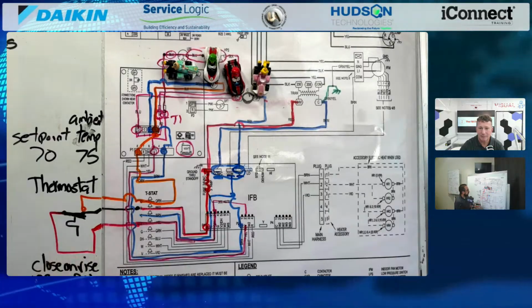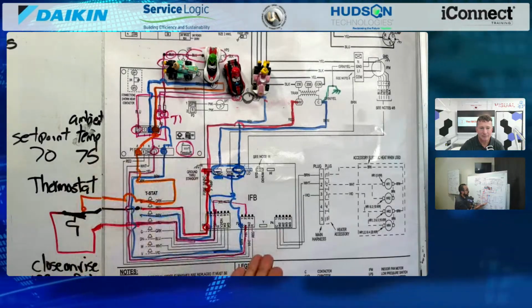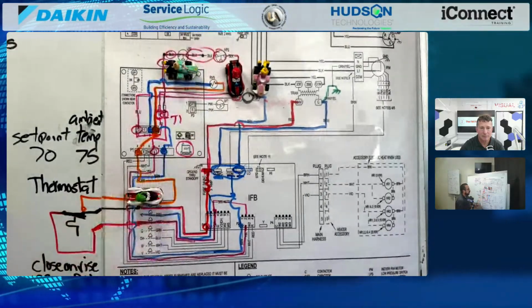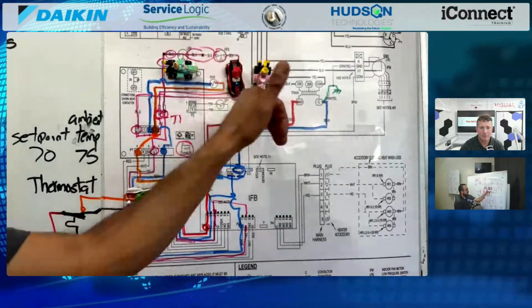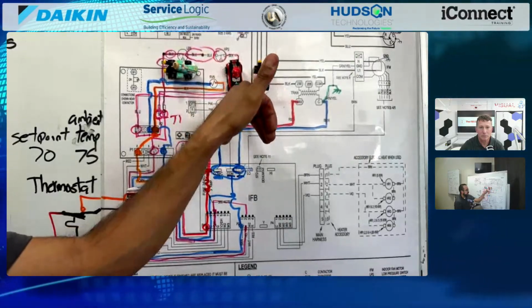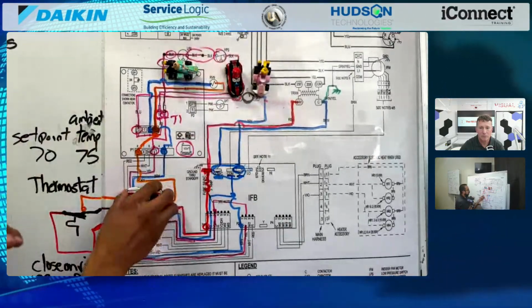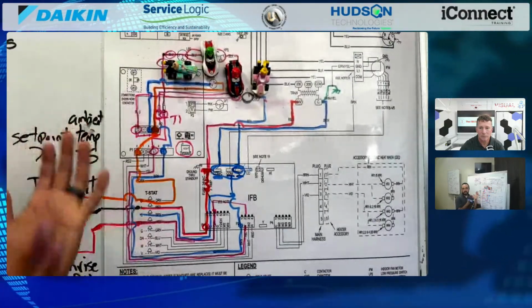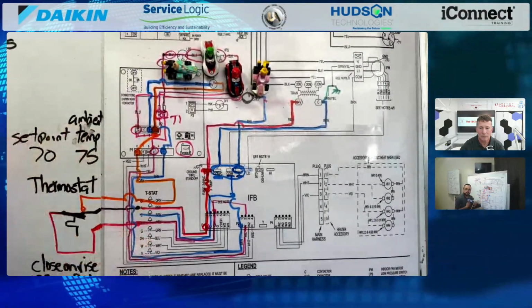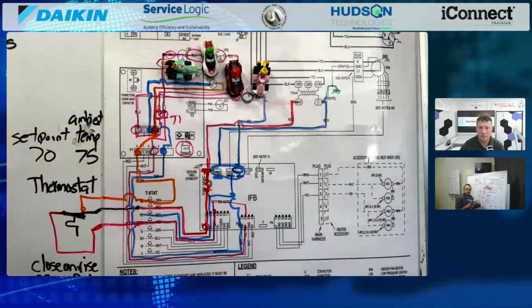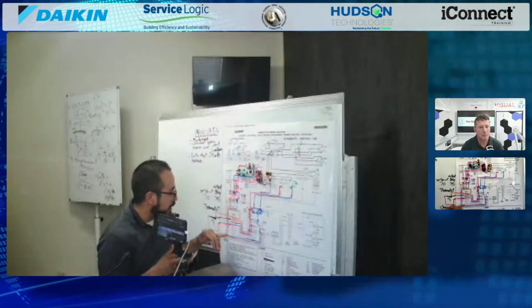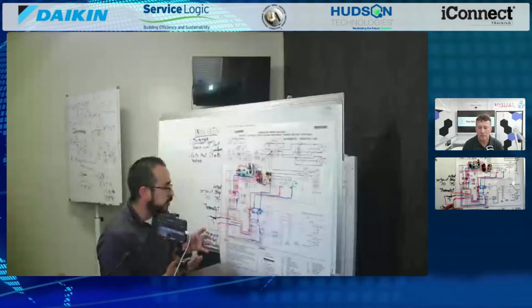Same thing too, if I have a call for heating, I'm not gonna send 24 volts there. So Luigi's just gonna go back and wait while I have heating, because this compressor needs the contactor to be pulled in for heating. But if I have cooling, Luigi just takes that path to make it to the reversing valve. Now I have cooling. So it's just switches, that's all you're doing, whether it's W or G, it's just switches.